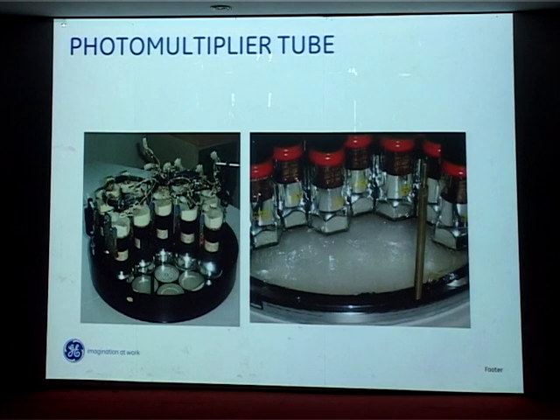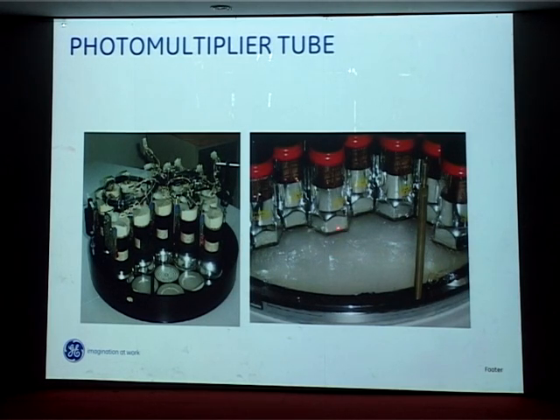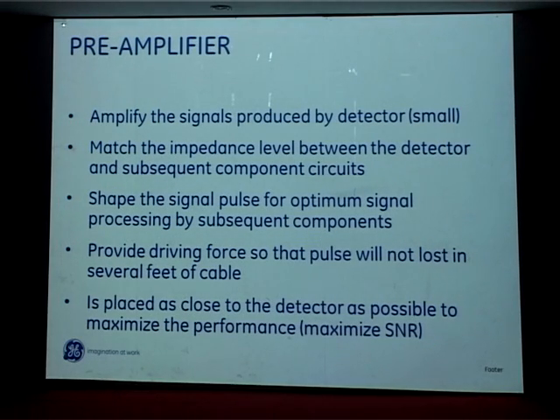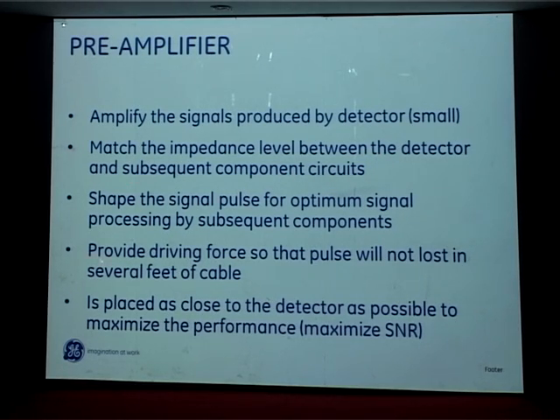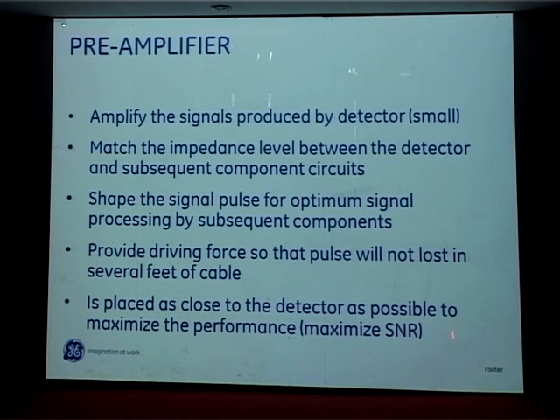This is how it looks inside an opened gamma camera — these are the photomultiplier tubes, and in the image you can see the photomultiplier tube, the crystal, and the optical coupling between them so there is no loss of light. The preamplifier amplifies the small signal produced by the detector, matches the impedance level between the detector and subsequent components, shapes the signal pulse, and provides a driving force so the pulse is not lost in the several feet of cable. It is placed as close to the detector as possible to maximize signal-to-noise ratio.